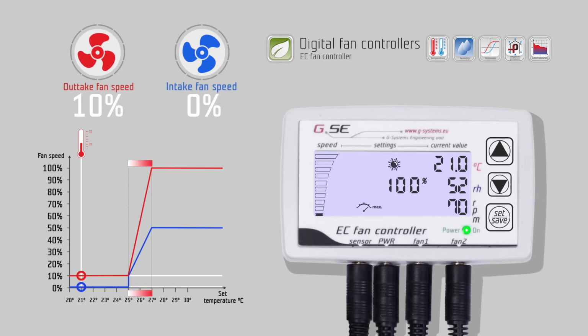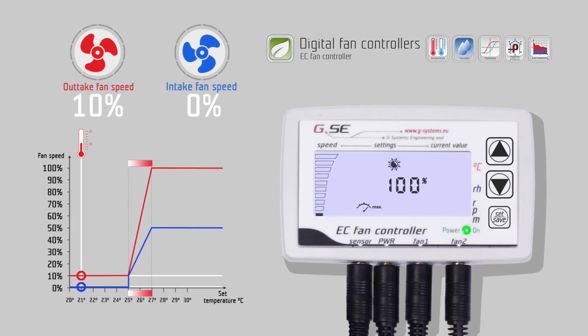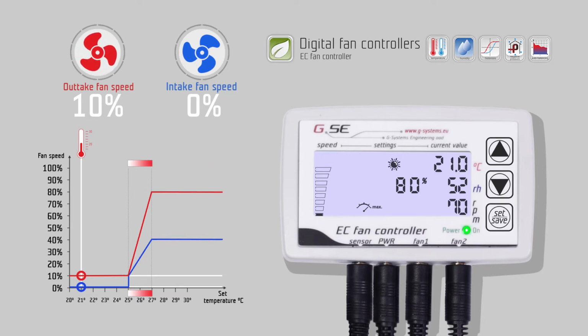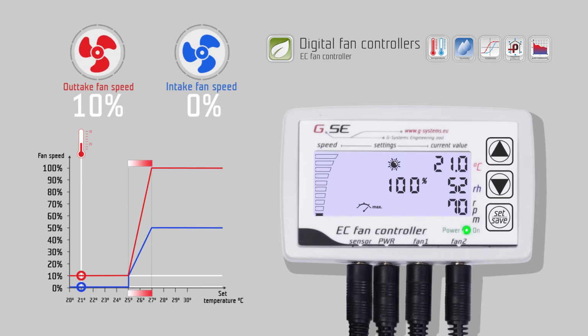Press down to go to the maximum speed day setting. The maximum speed setting also limits the exhaust fan, and should never be undercut during the regulation. The current maximum speed is displayed on the top side of the speed bar. Each missing segment represents 10% fan speed. For example, we set the maximum speed to 100%.